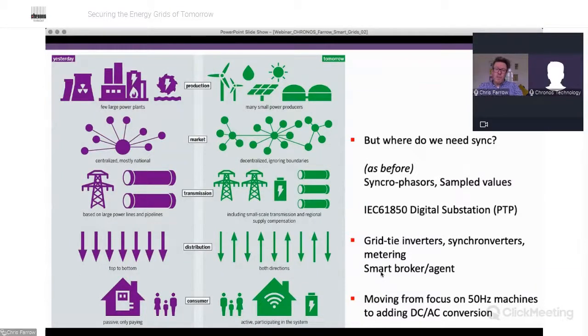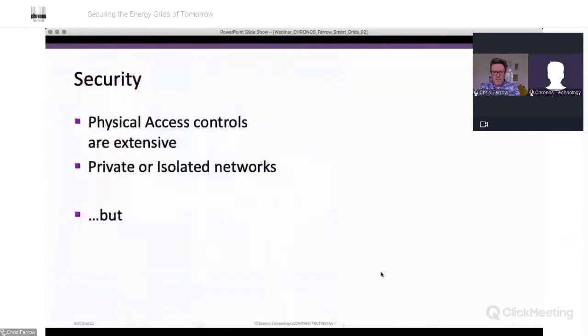The IEC 61850 digital substation specification calls for PTP, the Precision Time Protocol, which means we usually have satellite-based sources of time for the reference clocks, and the PTP clients in the IEDs within the substation are all using the same notion of time. There's also a level of synchronization required from the micro generation sources to make sure they're generating electricity in phase with the grid as a whole. So lots of requirements for synchronization and timing across that system.